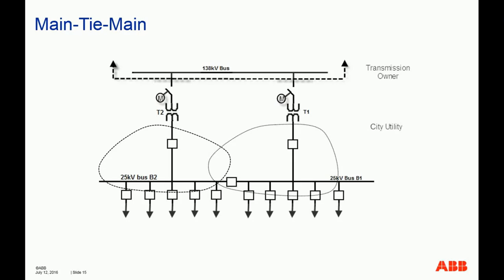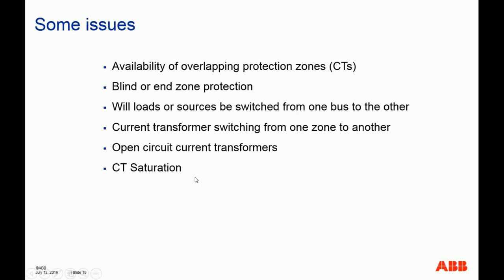This we call simply main tie main. We see that a lot usually in distribution, medium voltage level, and in industrial plants. So you have a tie breaker. The tie breaker can normally be operated as normally open or normally closed, and each of these two transformers should be rated to carry the full load of the bus. Okay. And you can have a dedicated bus protection to protect the main bus sections.